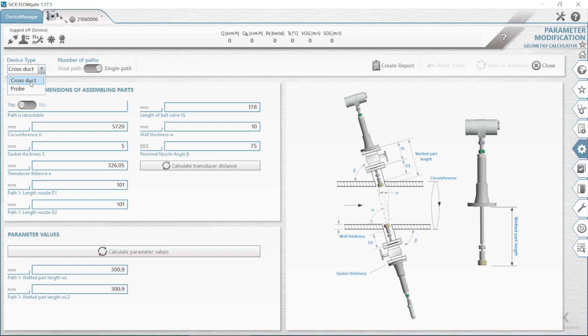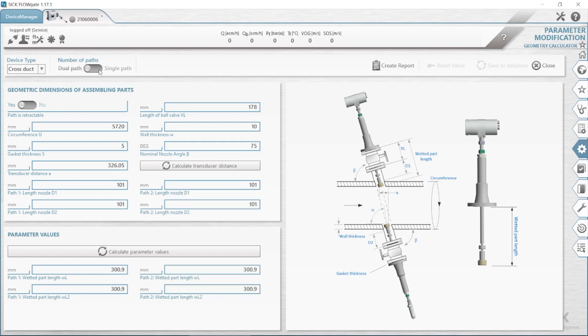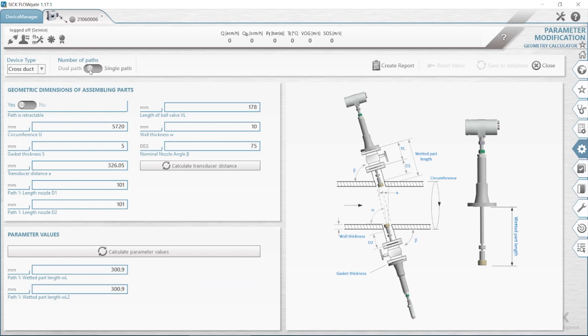So we can choose between a cross duct or a probe version. In our example, we will use the cross duct. Here is a slider where we can choose the number of paths — for instance, if we have a dual path — and in our example, we will use the single path. You can also choose with another slider if the path is retractable or not. If it is, the system will add a length for the ball-valve.